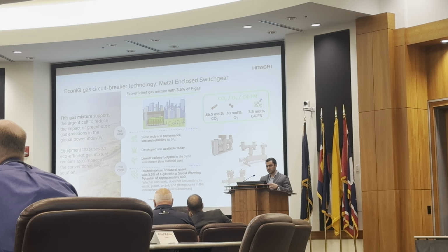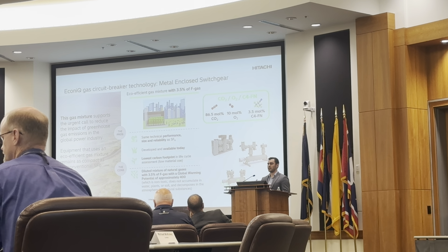And when it comes to different scenarios like gas monitoring, humidity or pressure monitoring, that gas is a homogeneous gas, right? The way the gas handling works is that before the substation is energized, the gas is mixed into a homogeneous gas, and that's the same way it's filled. So you're not taking the purity of each gas independently, you're taking the purity of the gas itself.